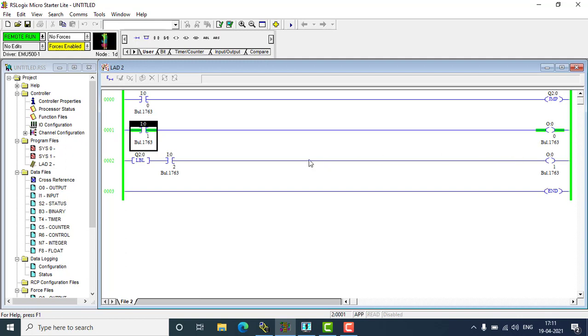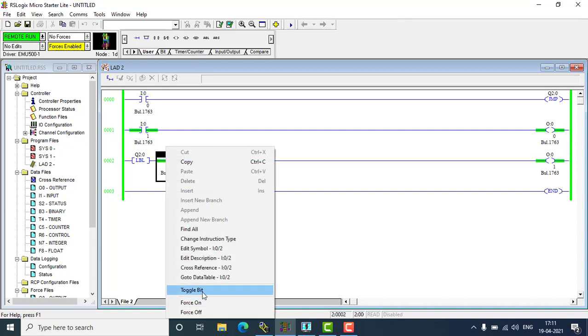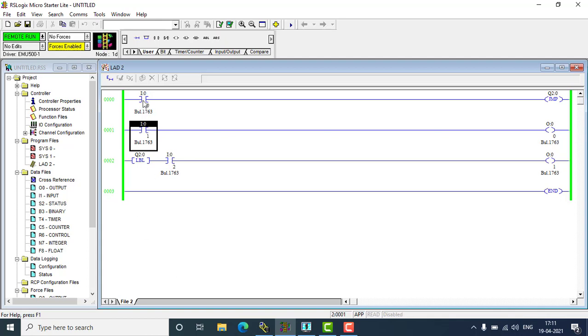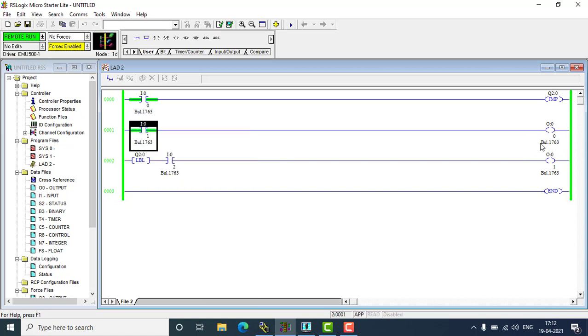I want to skip the output O:0.0 when my jump is on. In normal condition I'm going to enable the outputs — toggle, and the output is on. Second one — toggle again, and the output is on. Now I'm going to toggle them off, and I'm enabling the jump first — toggle. Now the jump is enabled and I'm going to try to turn on the intermediate output — toggle. You can see the output has been skipped; there will be no output if the jump is on.